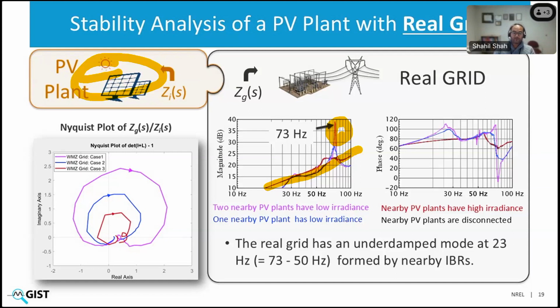So now let's see how our IBR impedance matches with this grid impedance. And then we plot these Nyquist plots here. So when we use the red grid impedance, which is when the other PV plants in the region have high irradiance, and match it with our PV plant that we are analyzing, which has low irradiance, the Nyquist plot doesn't encircle the critical point. It basically shows that the IBR plus grid are stable. And again, we do this without running any additional EMT simulations. You just need impedance responses.